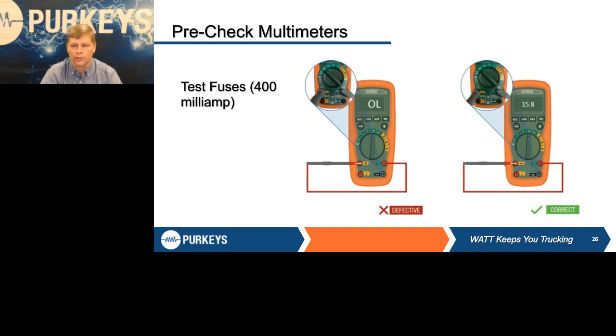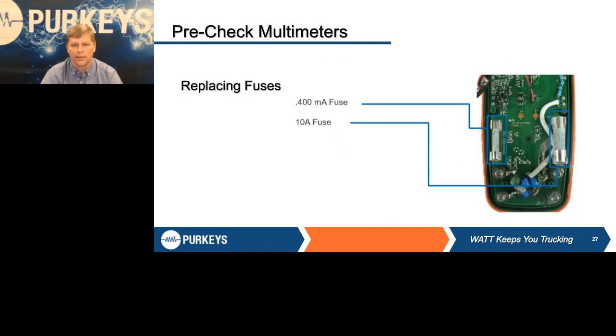I'll show you what those fuses look like. The one on the right is the 10 amp fuse, or again, depending upon the meter, it may be a 20 amp. The one on the left is a milliamp fuse. The one on the right can be $12 to $15 depending upon where you buy one. They're not cheap, so if you do something foolish, you're going to be spending money. If you do blow one of these, you do not replace it with a Wrigley's wrapper, a 22 shell, or a glass fuse out of your old Ford pickup. These are special fuses. They are designed to blow quickly if they need to protect your meter.